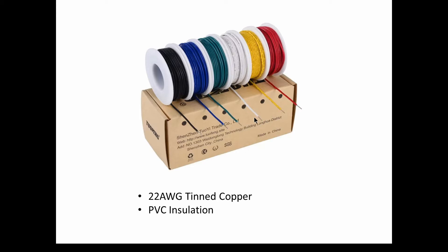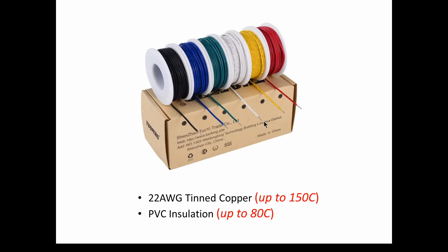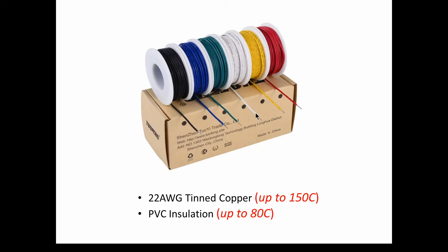So the first thing you got to think about is, okay, what are the ratings? What are these wires and the insulation, what are they capable of? Well, if you look online, you might see something about tinned copper that says, ballpark, you get up around 150 degrees C, that's the maximum in-service ratings. So you don't want to heat this up past 150 degrees C. Now, what you won't see is, what does that mean? Is it going to melt? Is it going to blow up? Is the house going to burn down? It just says 150 degrees C. Now, the manufacturer says for this particular wire, the PVC insulation is good up to 80 degrees C. So you don't want this wire, presumably, to get up near 80 degrees C because it might damage the insulation. Now, what does that mean? Does it mean if you get to 80.1 degrees, it's going to melt the insulation and it's going to catch on fire? Who knows?